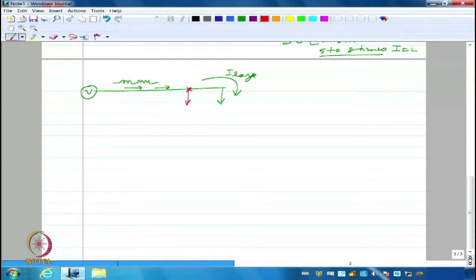So it is a short circuit. So you will see that the current drawn is very high, the voltage will dip. So it is really, really dangerous for the other equipment which require constant voltage. So you can't connect those equipment in the same line, or you should put a restriction on the equipment that can be used or it cannot be used. You have to say this is the limit.